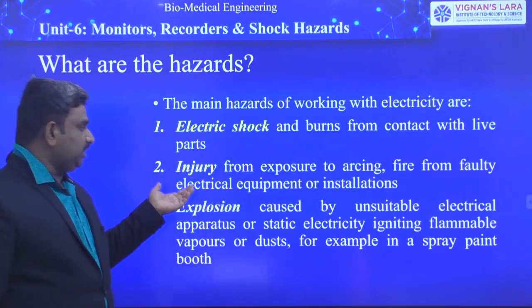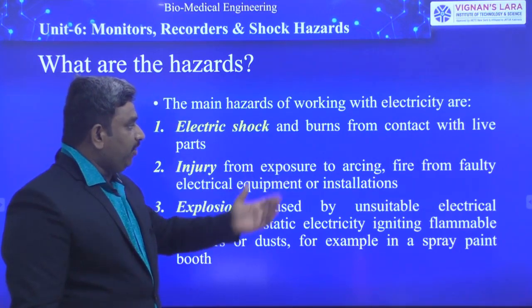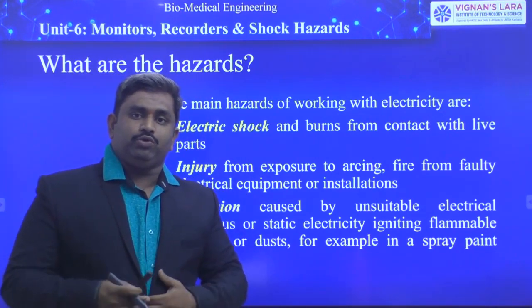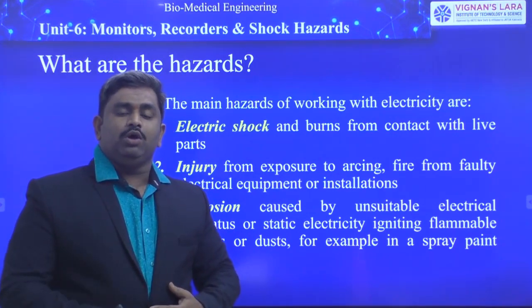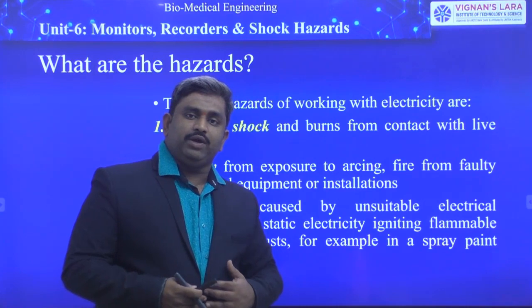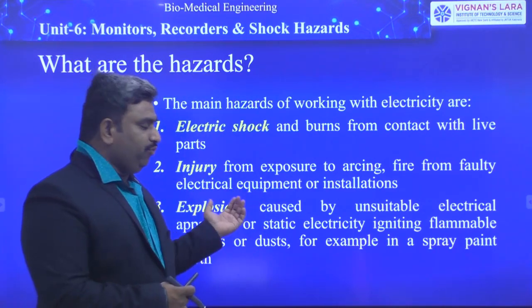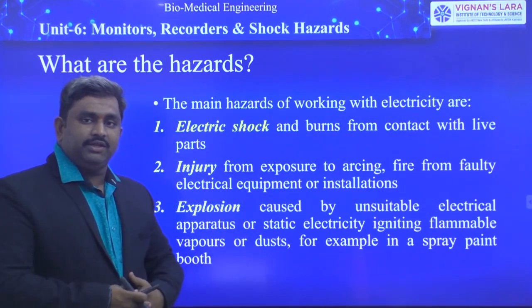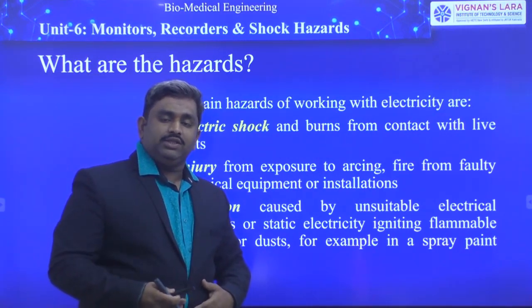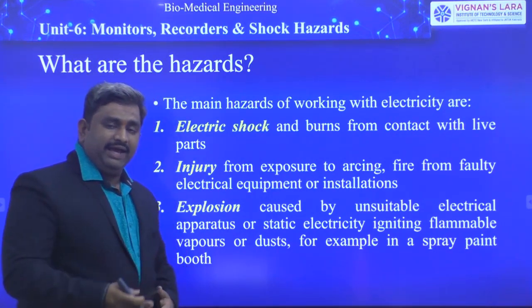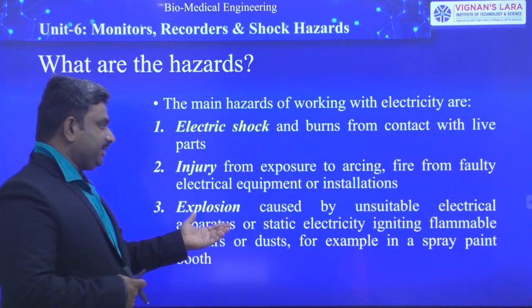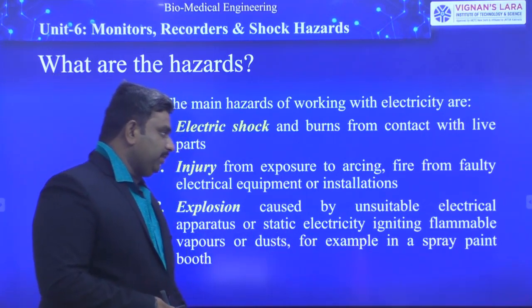The second point is about physical injury. Injury can be caused by arcing from faulty electrical equipment or installations. Due to faulty electrical equipment or uninsulated electrical wires, human body parts may be burned. The last situation is explosion, which may be caused by unsuitable electrical apparatus or static electricity igniting flammable vapours or dust, for example in a spray paint booth.